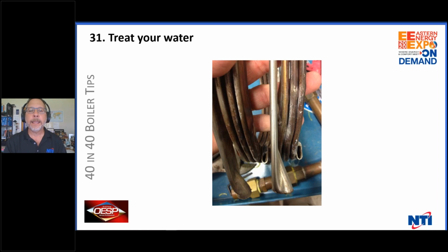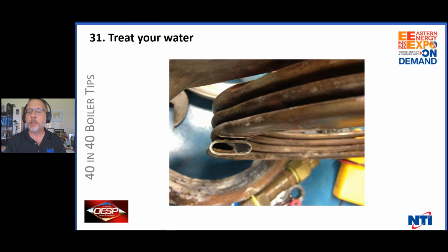Oh my God. Yes, the system was full of it and they weren't moving the system fast enough. Let me zoom in on it. That's hard as concrete. And you know how you know this is happening inside your modulating condensing water tube boiler? Because it percolates. That's when it's light. It just percolates. It percolates because of the steam explosions happening inside that magnetite that's hard as iron. The water absorbs into it during the off cycle. When the boiler starts up, it creates steam pockets, which will erode the stainless steel and eventually make a leak.